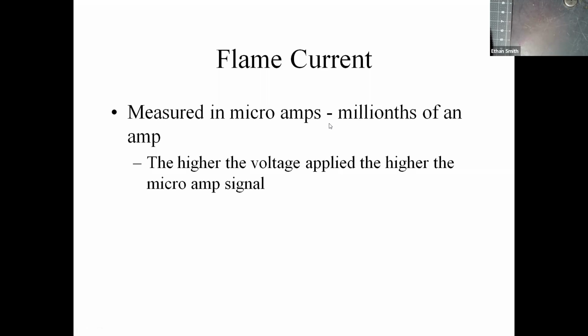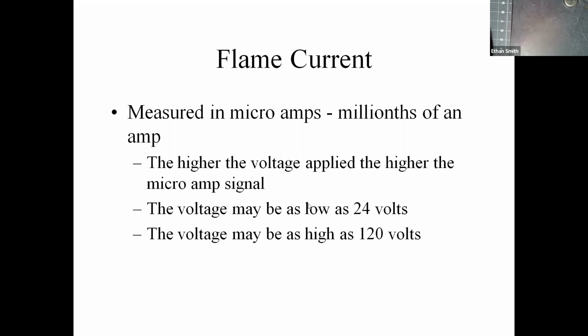Okay, so the higher the voltage, the higher the flame signal you're going to get. So you'll see some equipment run 24 volts up to that flame sensor, and some of it runs as high as 120 volts. The modulating furnaces guys almost universally run 120 volts through that flame sensor because they've got very little flame to deal with. And so they need to boost that flame sensor as high as they can get it.